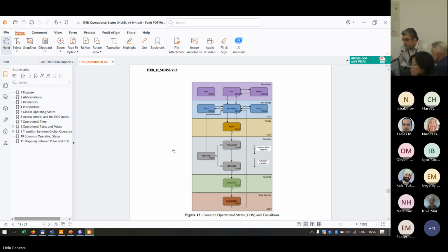Well, I don't know which diagnostic you're from, maybe it was written somewhere. But it seems that there is the erosion monitor G8. Erosion monitor. So this is something like a laser that is inserted in the vacuum vessel. Okay, well, that's a typical kind of interlock example, which we'll perhaps discuss tomorrow. But it seems to me that the pulse shall not start if your diagnostic is deployed. Now you can say SOUP is good enough to protect against this mistake. Or you can say SOUP is not good enough because SOUP is not really an interlock system.